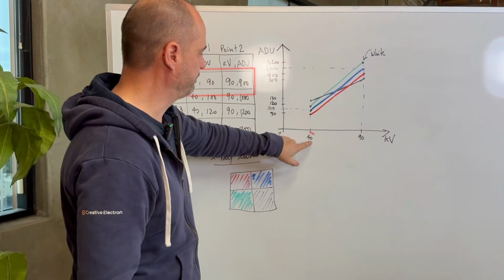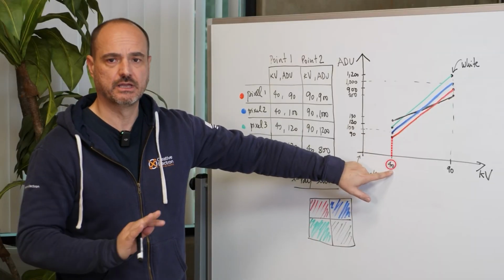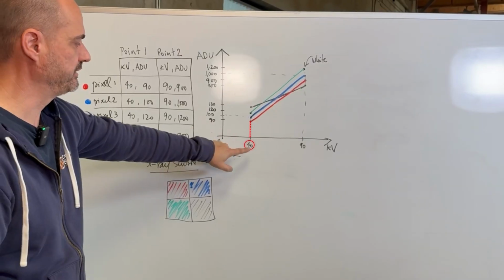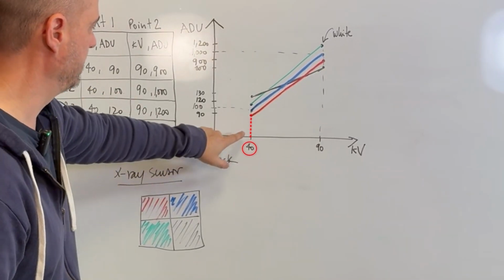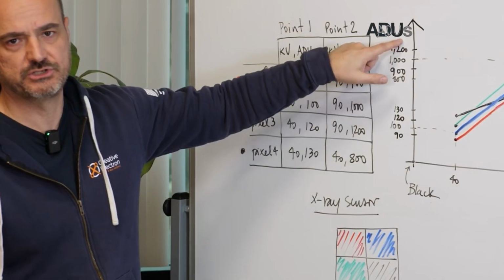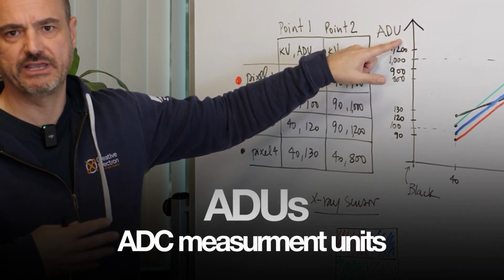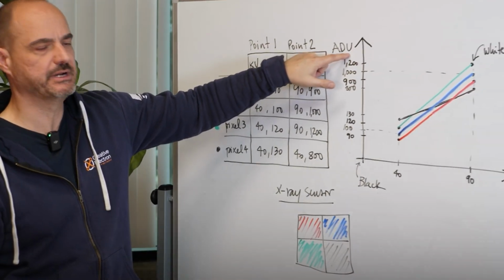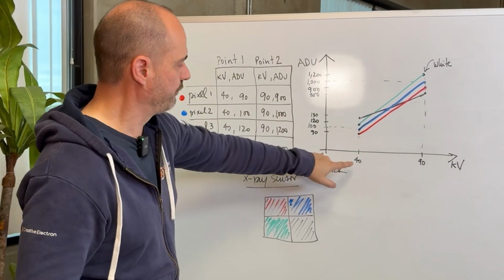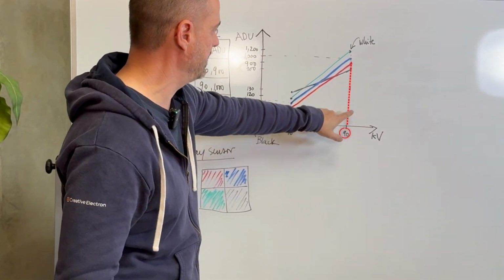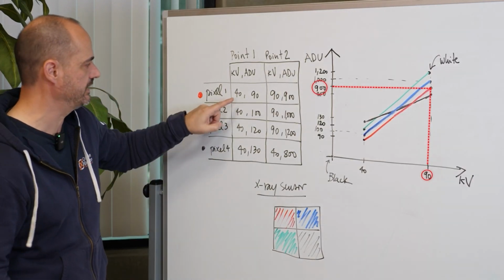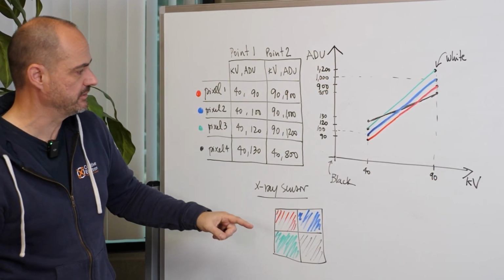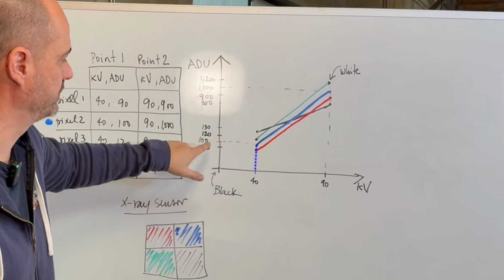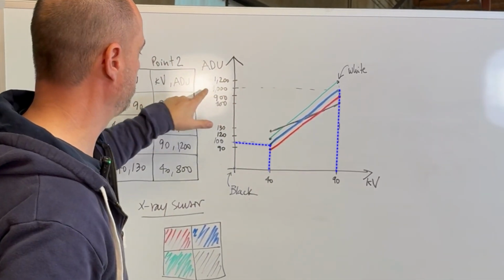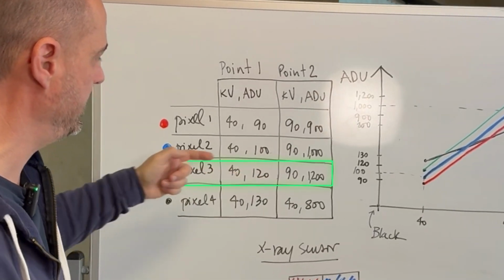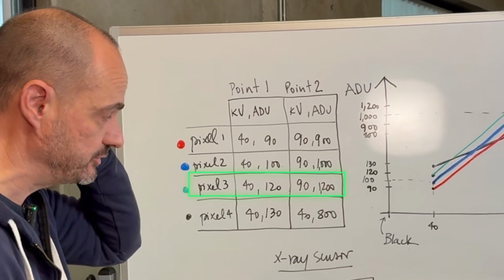Pixel 1 here, if we put 40 kilovolts, and the same amount of current for all these experiments, we're going to have 90 ADUs, which is ADC measurement units. ADC is analog to digital converter, so that's the number that we're getting out of our ADC. So 40 kV, 90. If we go to 90 kV, we're gonna get 900 ADUs. Now, the next pixel, just next to it, at the same 40 kV, gives us an output of 100, and 90 kV gives an output of 1,000. The third pixel, 40, 120. And at 90 kV, we get 1200 out of the ADU.